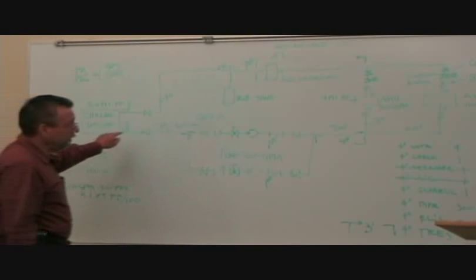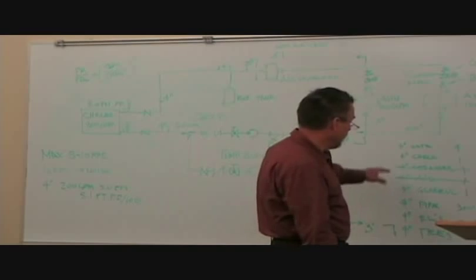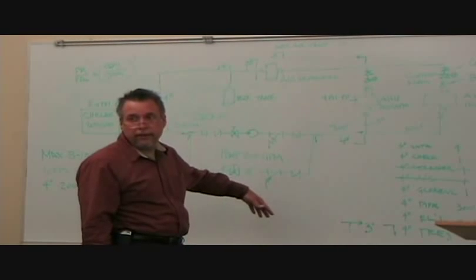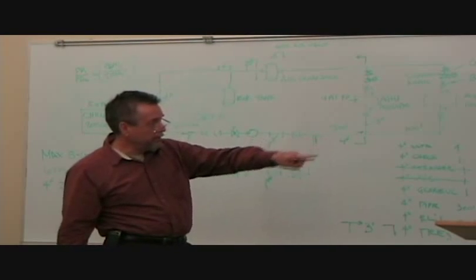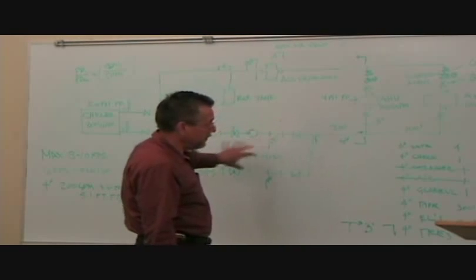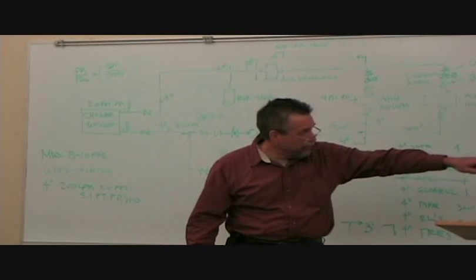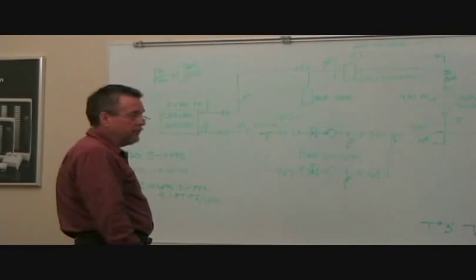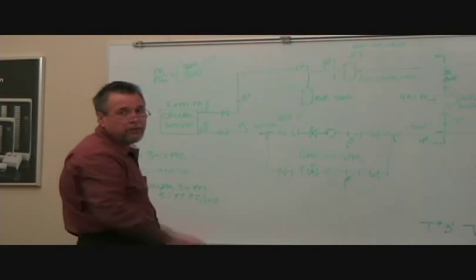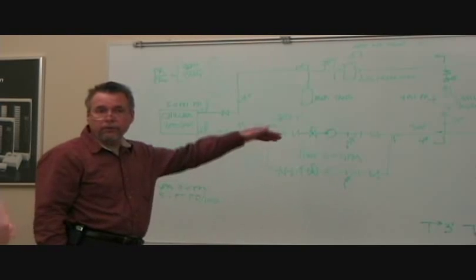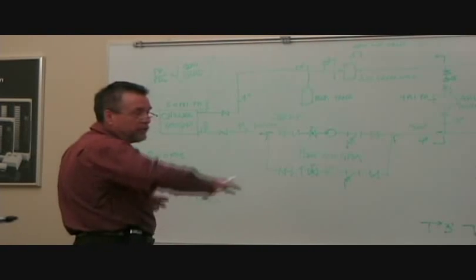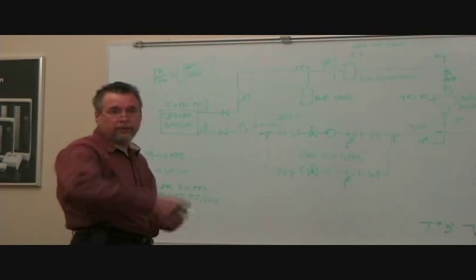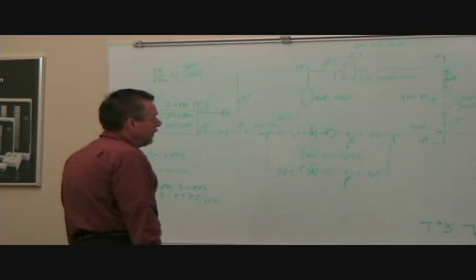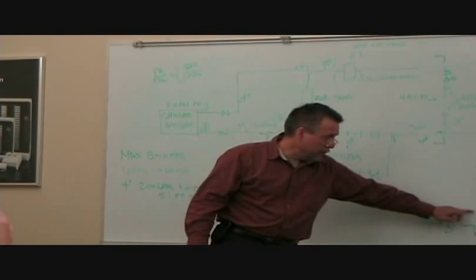So you can see, kind of the point I'm making is piping, yes, it's critical, but if we take all the components out, piping was about 50% of my pressure loss for the entire system. And this is pretty standard. These rules of thumb are going to hold unless I've just got a huge building or a campus where I'm running thousands of feet of pipe. So you can see elbows.